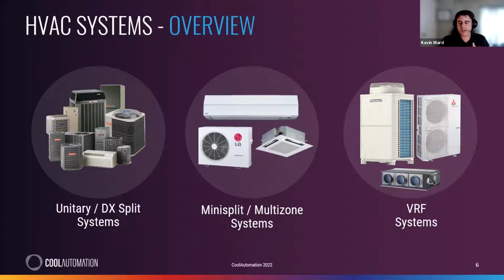The thermostat, when unsatisfied, sends a signal out to your condenser, the compressor kicks on, and you get cooling. This is probably the most common or popular type of HVAC system in North America, but we've started seeing exponential growth of mini split and VRF systems introduced into North America as well. The main difference between these systems is the type of compressor and the communication between the indoor and outdoor unit. Unitary systems are one-way, just on or off, whereas mini split and VRF systems are two-way, with an inverter outdoor unit that ramps up and down to match the load being called for from inside. There's a lot of confusion between a mini split or multi-zone system and a VRF.